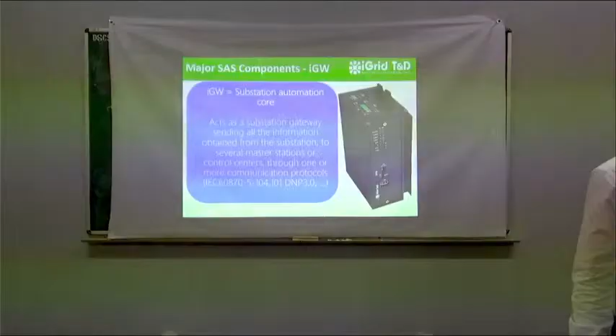If the main server or the gateway is not working, it will give a notification. It will automatically detect the issue and automatically do a switchover, so the standby becomes active. Once I have rectified the gateway or the SCADA server, I can do a manual switchover to make the primary the main server again, and the standby will continue in manual.